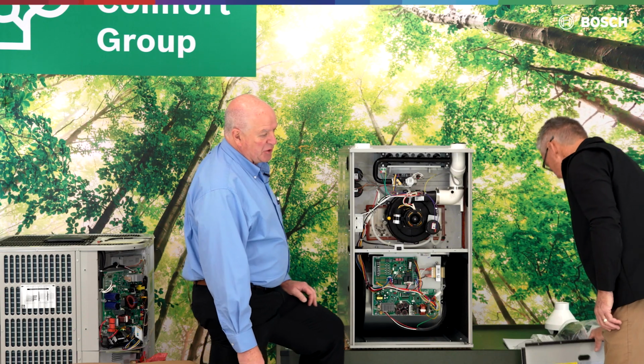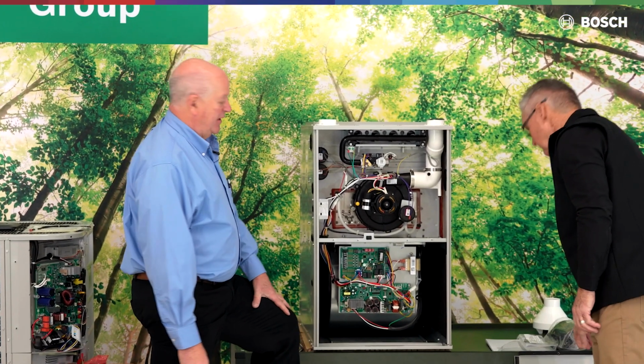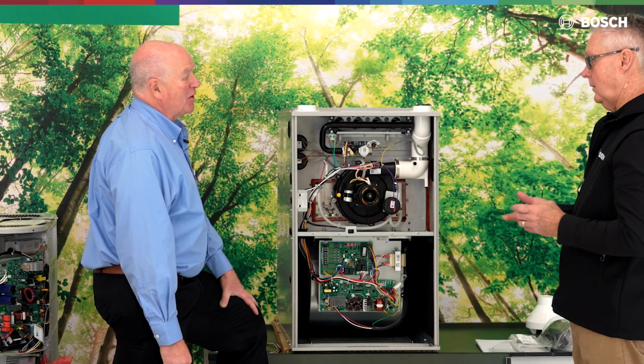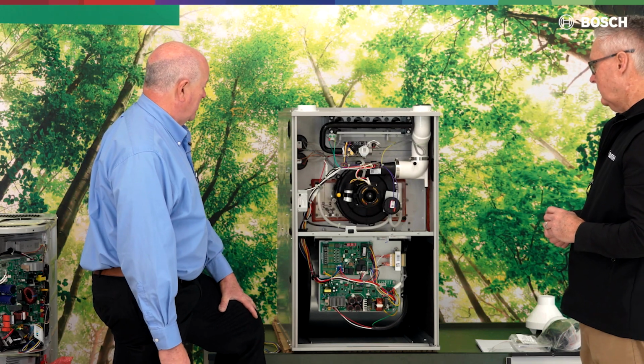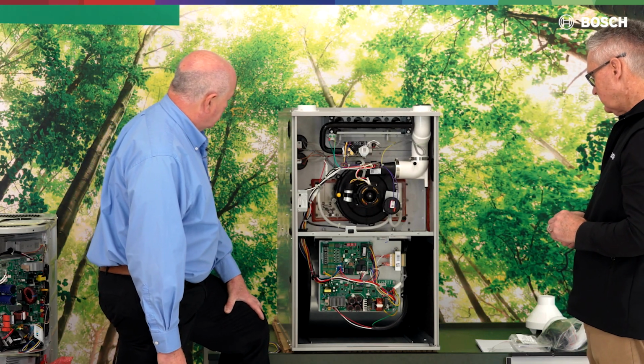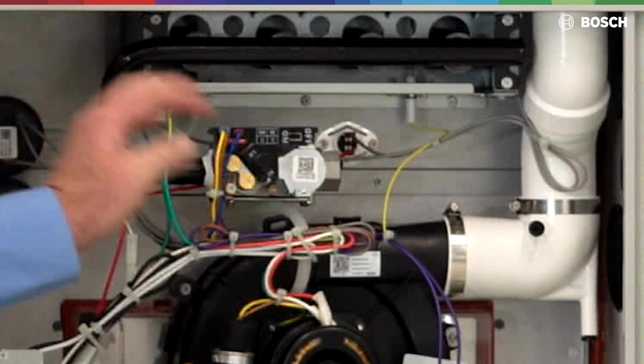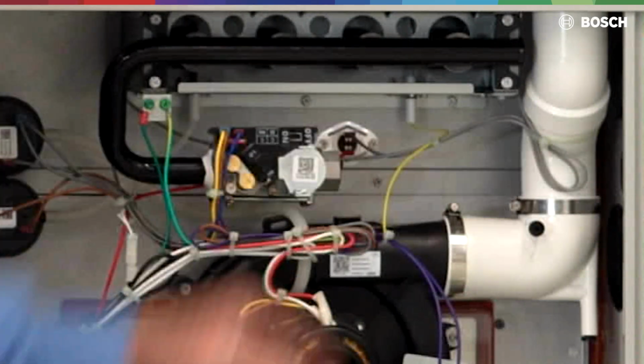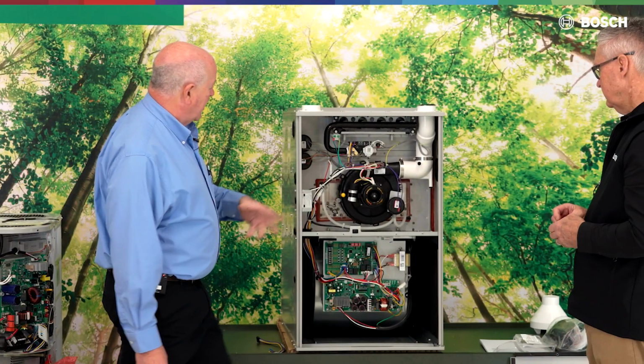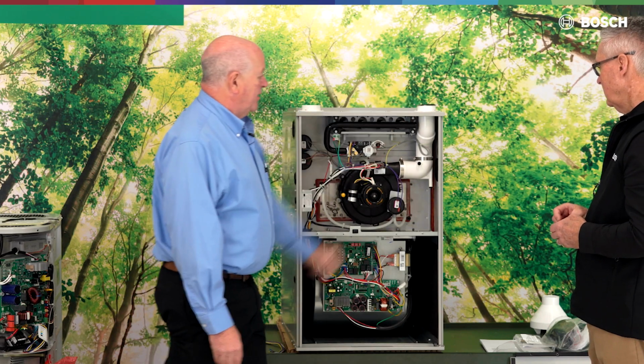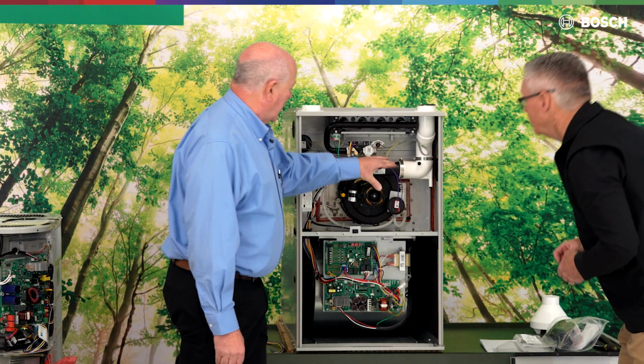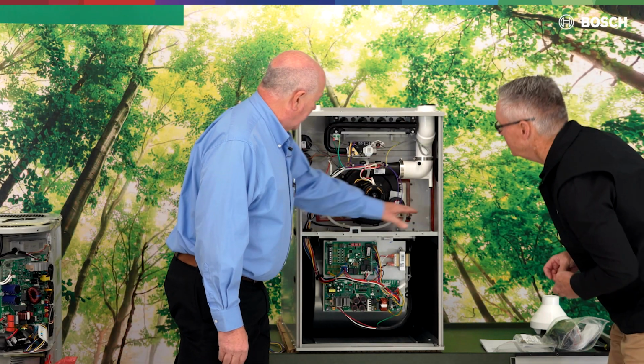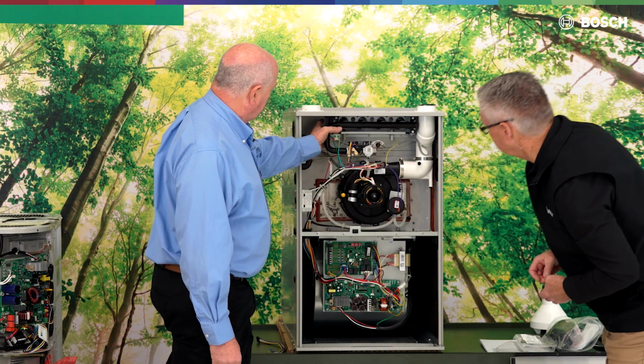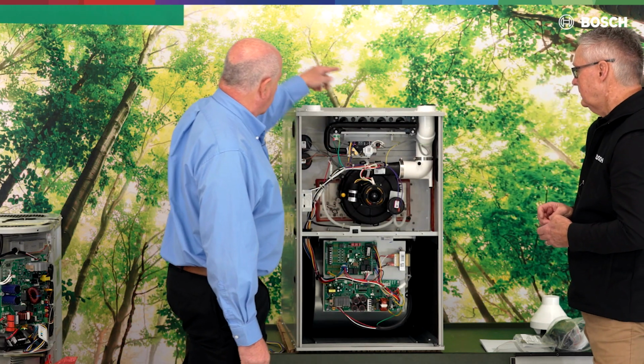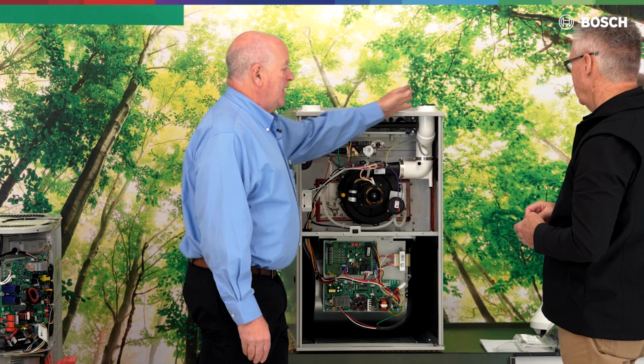So that polarity deals with our spark ignition. If we don't have the right polarity, we can't get the ground to create the spark, and that's where that fault comes in. So you have to have your ground and your spark. We have some sensors in here, rollout sensors. There's a rollout sensor on the side, and a high limit sensor here in the bottom. If you're getting rollout sensors, a lot of times that deals with the flue, the draft. If we don't have proper draft going up, if we have high pressure, or water building in the box, we can build up resistance of air going through the secondary chamber, primary chamber, and out that flue.